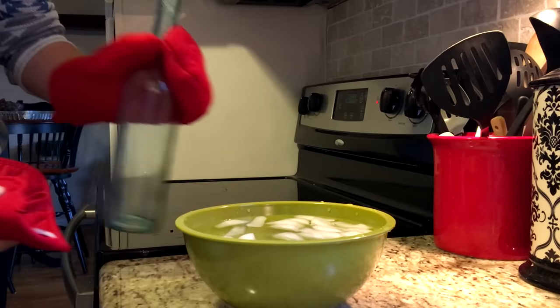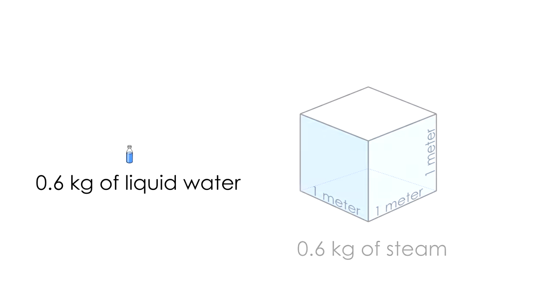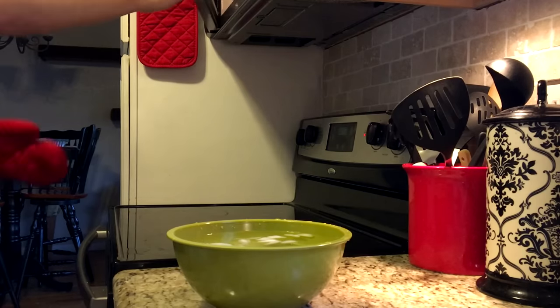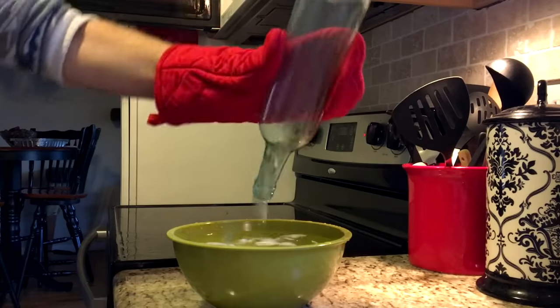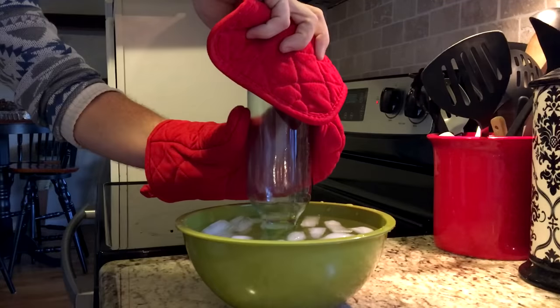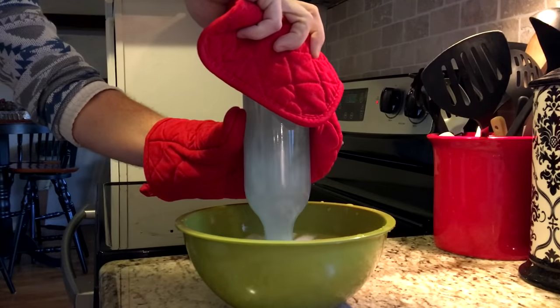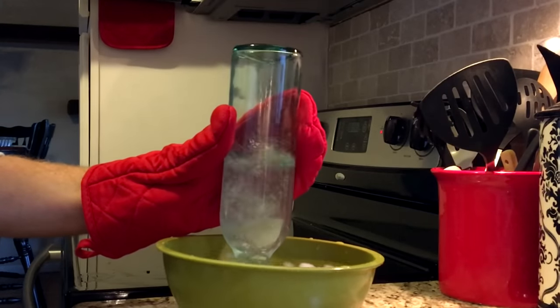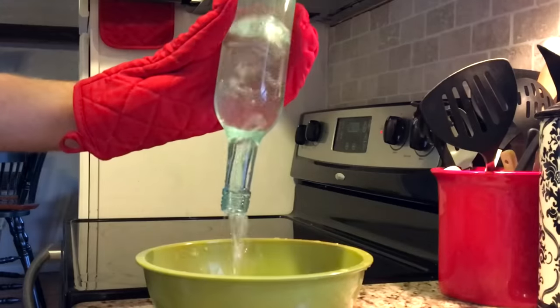There are several problems that condensate can cause, and we'll talk about two of them in this video. The first one is thermal shock. Imagine this: you open a valve allowing steam to flow into a steel pipe. As the steam comes into contact with that cold steel, it condenses. The problem is that steam takes up about 1,600 times more volume than its equivalent mass as a liquid. So when it condenses, it literally shrinks. In a closed container, like a pipe or this glass bottle that just came out of my microwave, that collapsing steam can lead to catastrophic damage. Water rushes to fill the vacuum created by condensation, cooling the steam even further and creating a runaway situation. This can happen extremely fast, and all that water can accelerate and decelerate violently. Hence the name steam hammer.